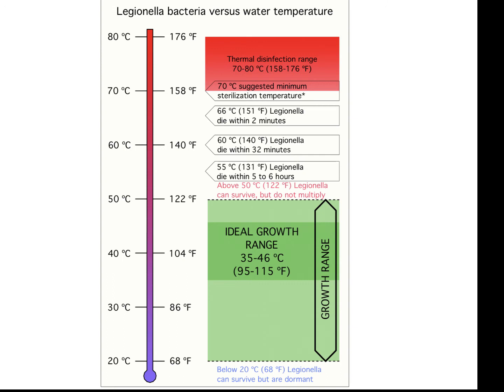If this is a new heating system, a new domestic hot water distribution system, there should be anti-scald valves at the point of use. And if that is the case, then the distribution system can also be raised up to a scald sanitization temperature that will avoid the production of Legionella within the distribution system itself. Although it's important to maintain a storage tank at a temperature above that, if you are not maintaining the distribution system at an adequately high enough temperature, it is entirely possible that bacteria can survive and, in fact, in some cases, thrive and cause the potential for people contracting Legionnaire's disease.